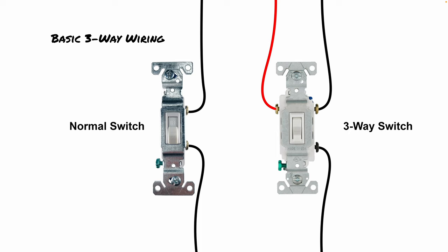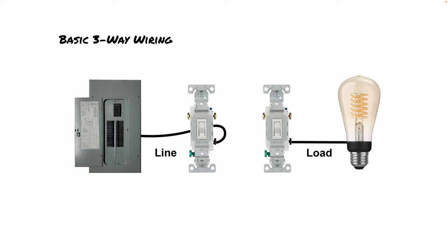I also want to talk about the difference between line versus load. We talk a lot about this when it comes to GFCI receptacles, but it also applies to light switches and especially three-way light switches. Basically, the line is when you have power coming in — so whenever power is coming into something, that's the line. In this example, power is coming directly from the breaker panel into the first switch.